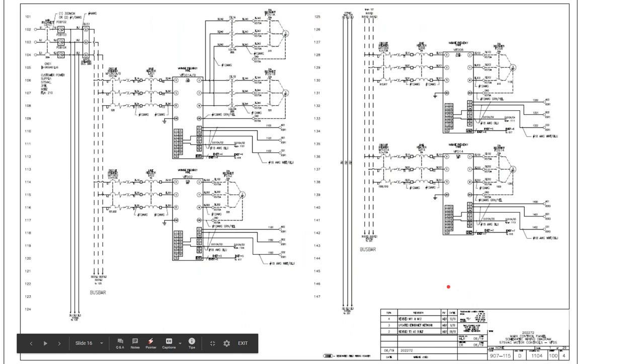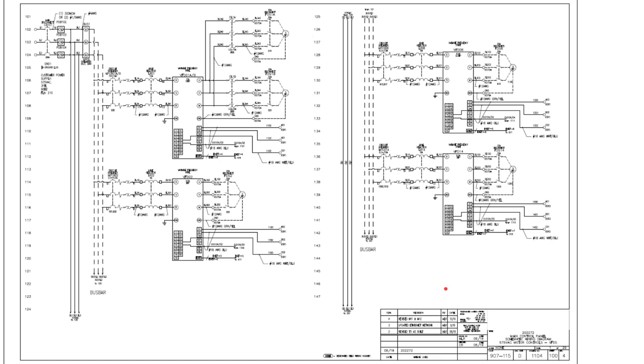Looking at the diagram, at the very beginning our panel needs power connected to it. Almost every single panel will have a main disconnect. In this case it's a circuit breaker type disconnect with a ground lug, and the drawing tells the installer exactly what type of power is required — in this case 575 volts, three-phase, 60 Hz — and the full load amps of the panel, which is 210 amps.